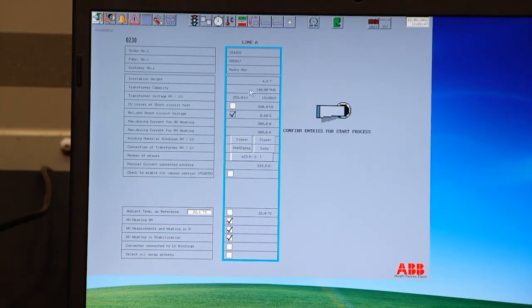Then comes the transformer capacity, MVA, found on the data sheet. You have the kilovolt ratings for the high voltage and the low voltage windings. Here it's important to take the right kilovolt according to the tap changer position. You should have as long a winding as possible. And in this case, where we have a 2-winding secondary side, you should try to have the equal voltage range of both windings.